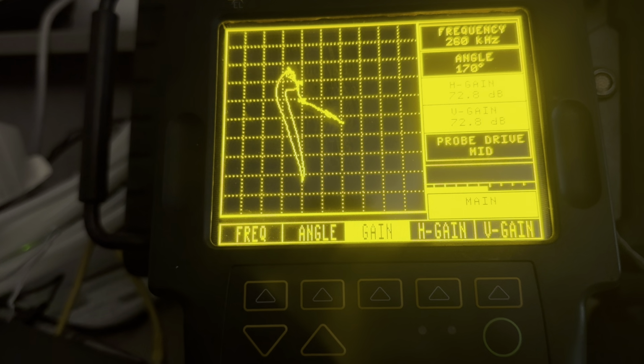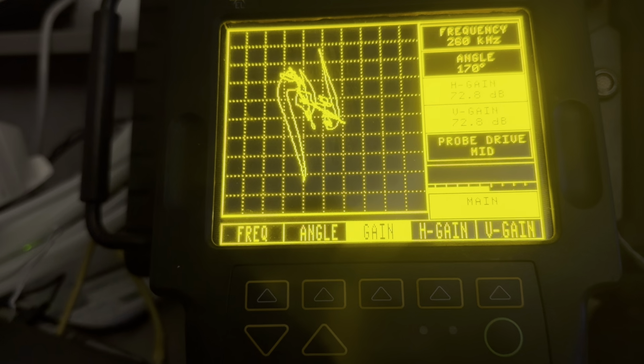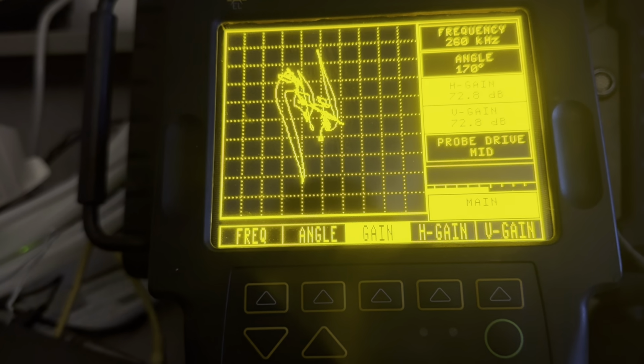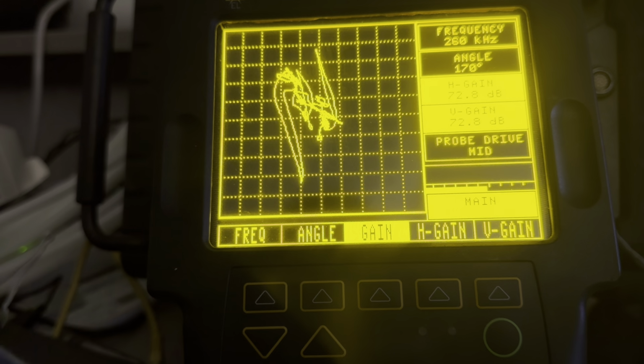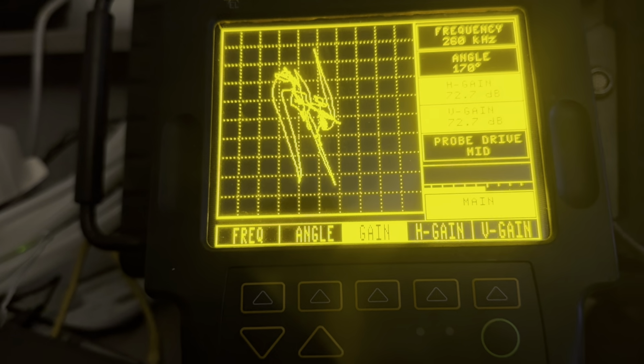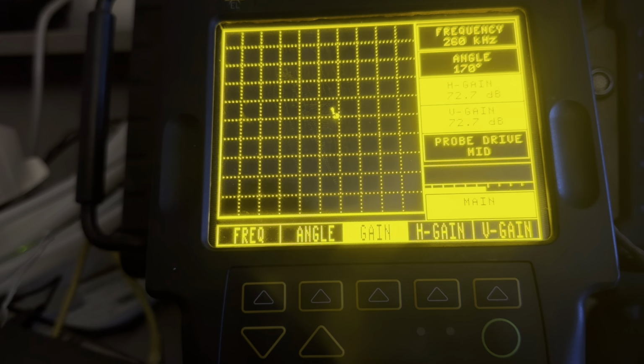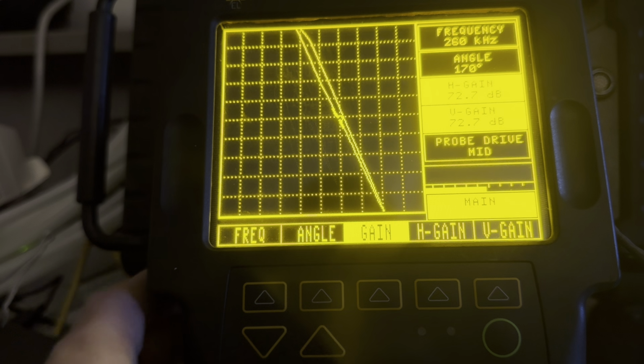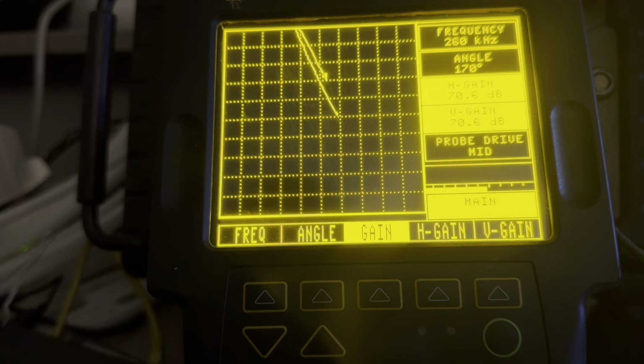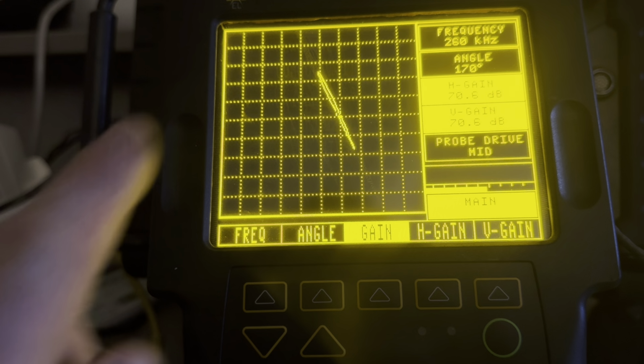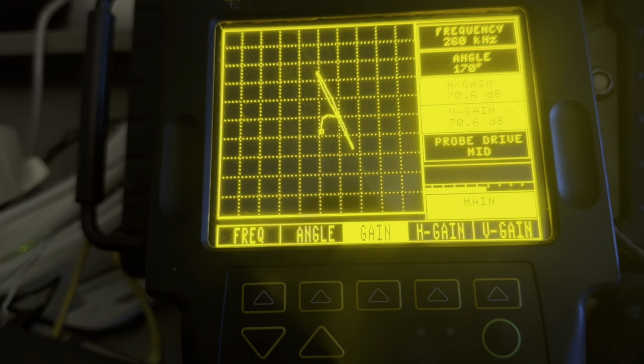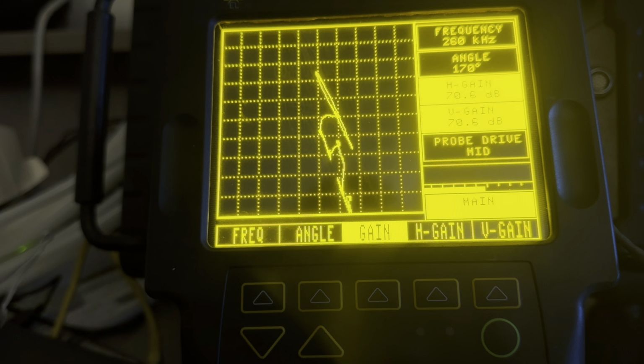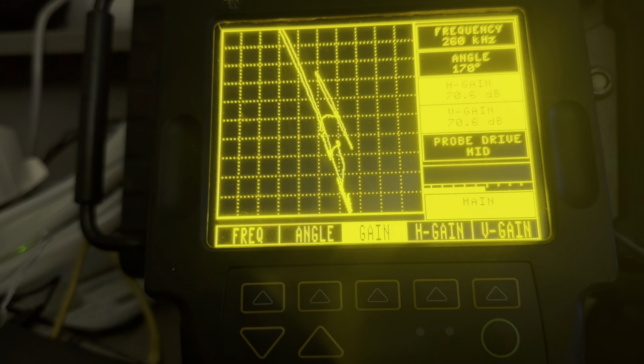That's the dual polarity. Actually, it's single polarity, vertical down. And if I rotate, it goes vertical up. Those are both single polarity indications. Let me see if I have, I think I got a hole here somewhere. Now this is an aluminum plate. I'm going to see if I can give you an example of a dual polarity indication. There we go. See that down and up? That's a pretty big hole that I'm going over there. But both coils see it, so you get a down and an up. But when you get linear indications preferentially oriented in either the axial or circumferential directions, then you'll just get the single polarity. Okay, what probe should we move on to next?